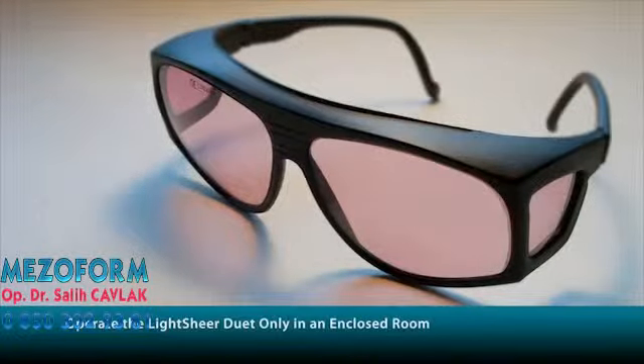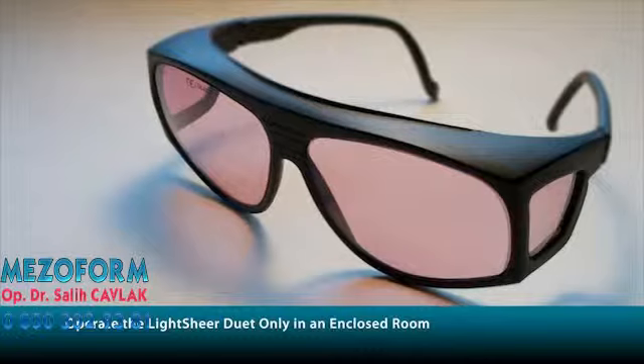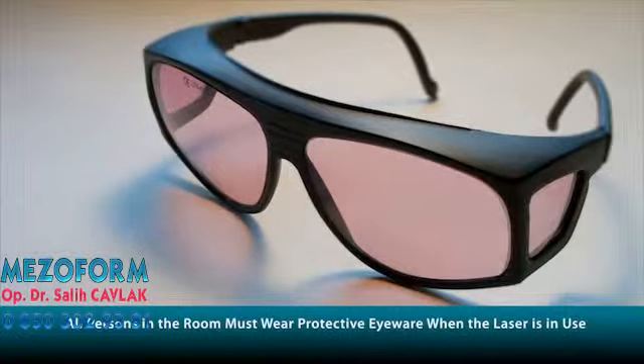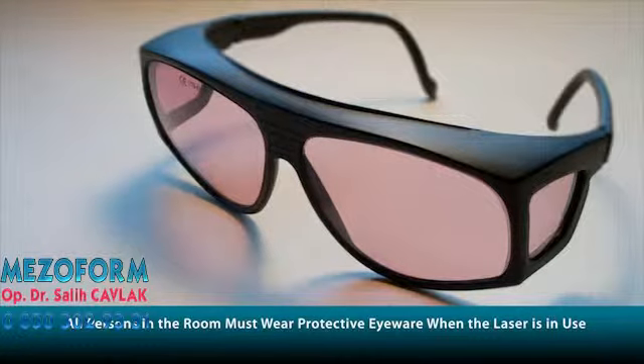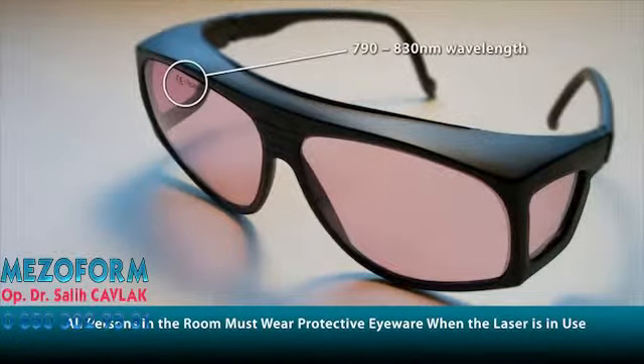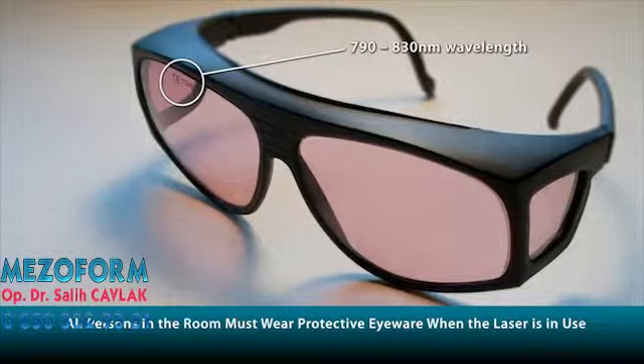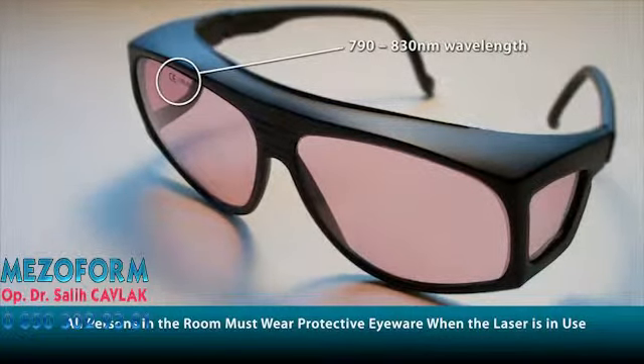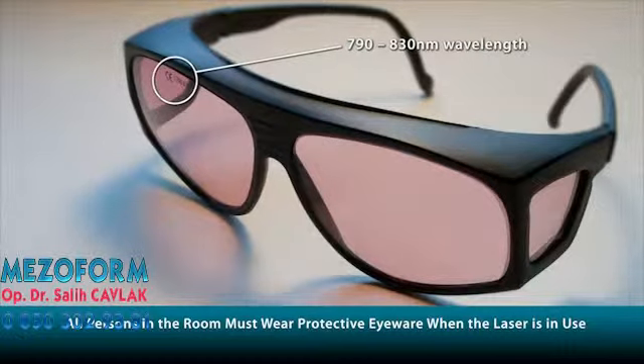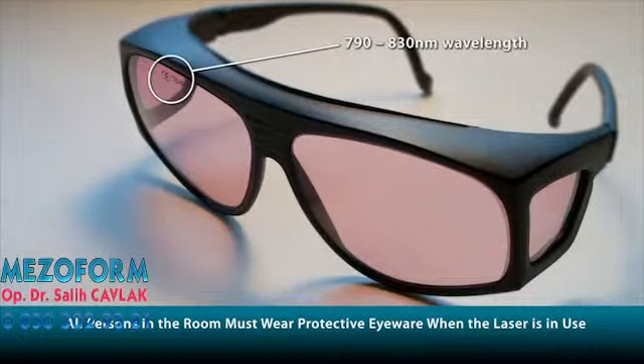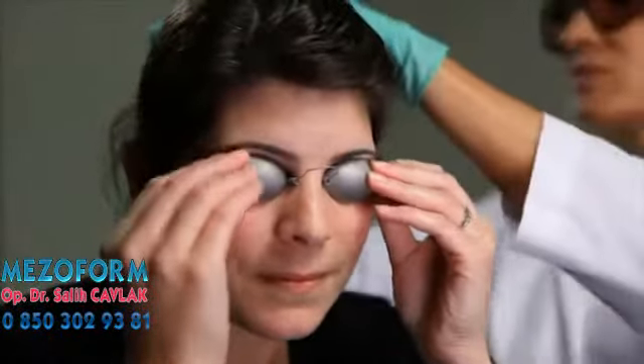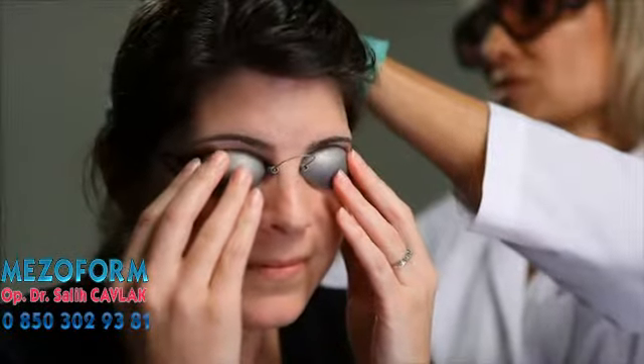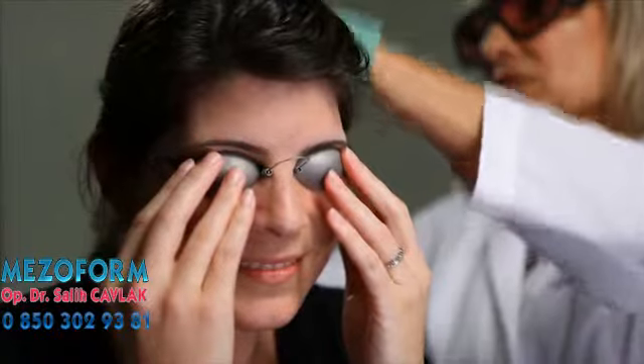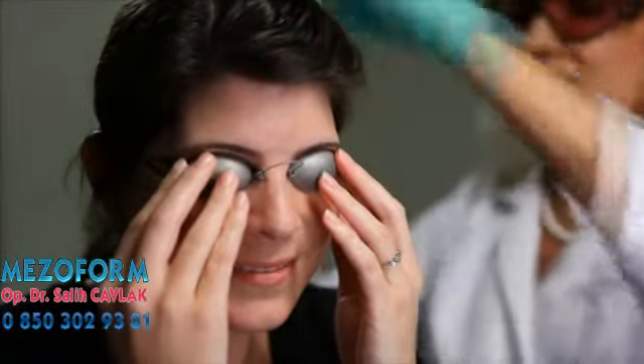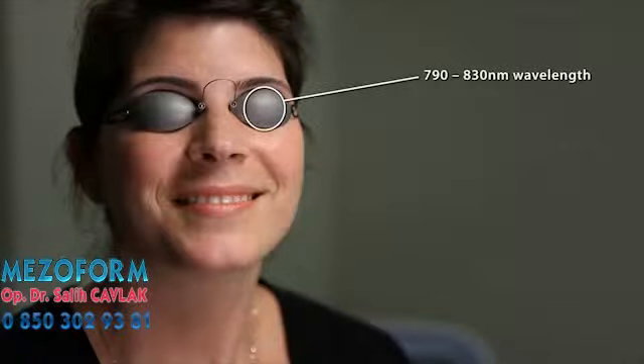The LightSheer Duet system is to be operated in an enclosed room with protective eyewear for all persons, including the patient, whenever the main power and key switch are turned on. The protective eyewear must have an optical density of 5 or greater at a wavelength of 790 to 830 nanometers. Contact your local service representative for additional information. For maximum safety, opaque or metal goggles must be worn by the patient for all facial treatments. Do not treat eyebrows, eyelashes, or other areas within the bony area surrounding the orbit.